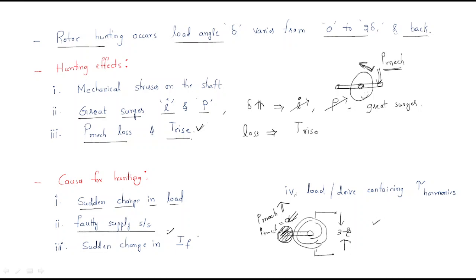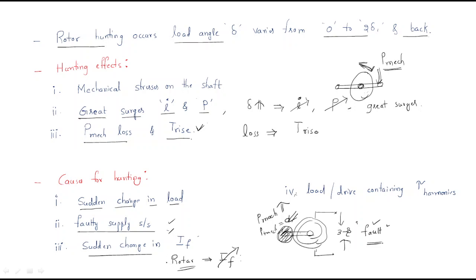Second cause: faulty supply voltage. If the supply voltage has a fault value — a wrong value — hunting will occur automatically. Third cause: sudden change in field current. If the field current connected to the rotor is suddenly varied, hunting will occur automatically.